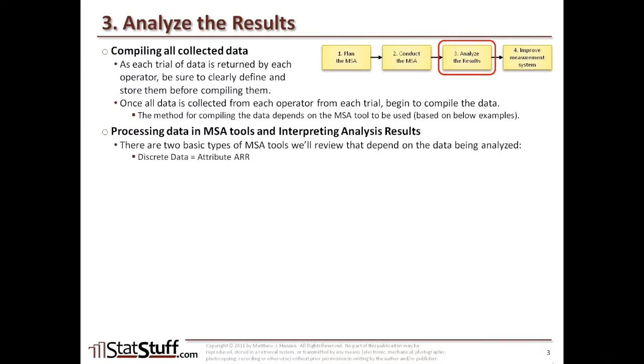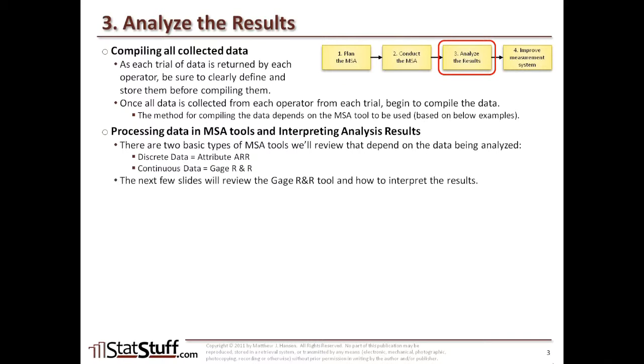The type of tool depends on whether you have discrete data or continuous data. If it's discrete data, we're going to use the attribute ARR test; if it's continuous data, you can use the gauge R&R test. For this particular study, we're going to look at the gauge R&R tool and how we can interpret the results.